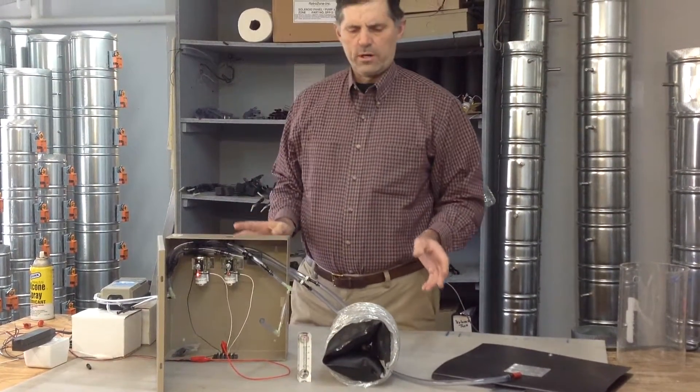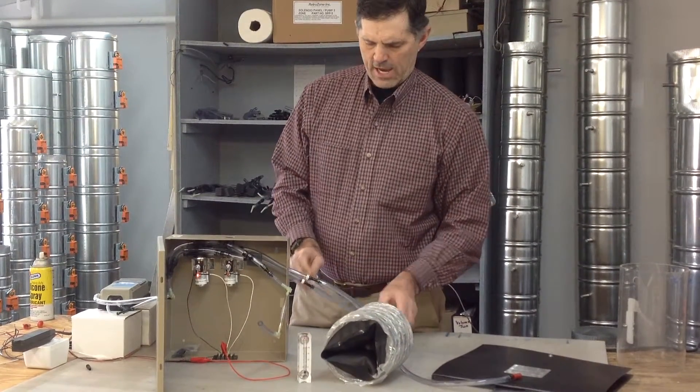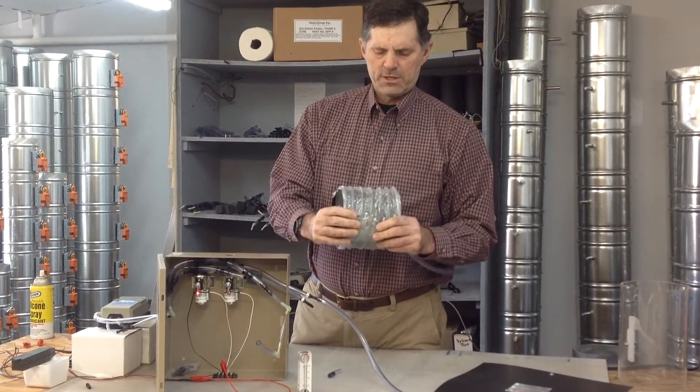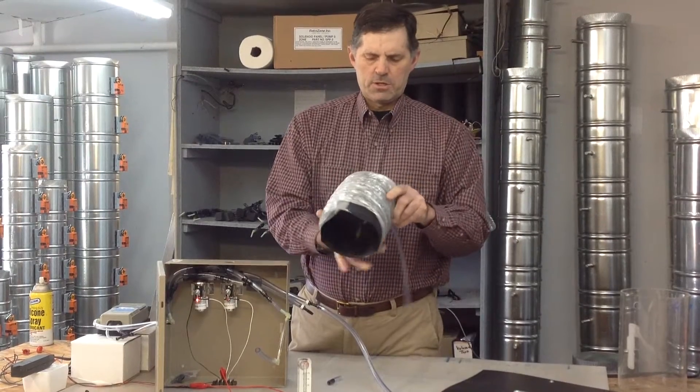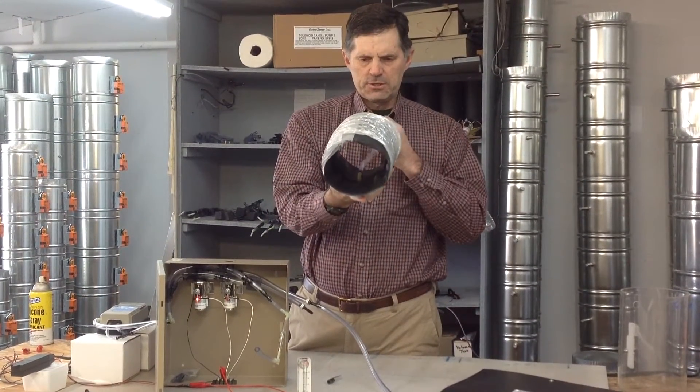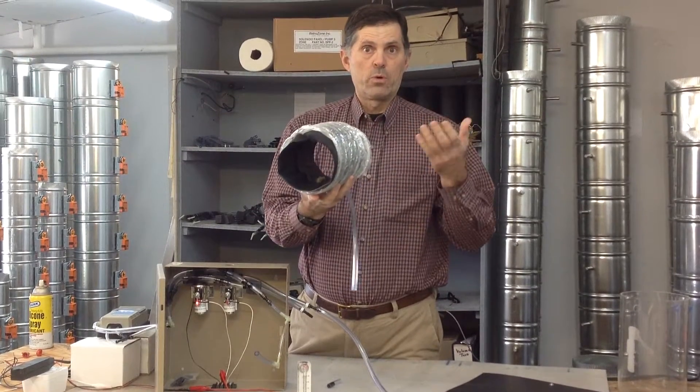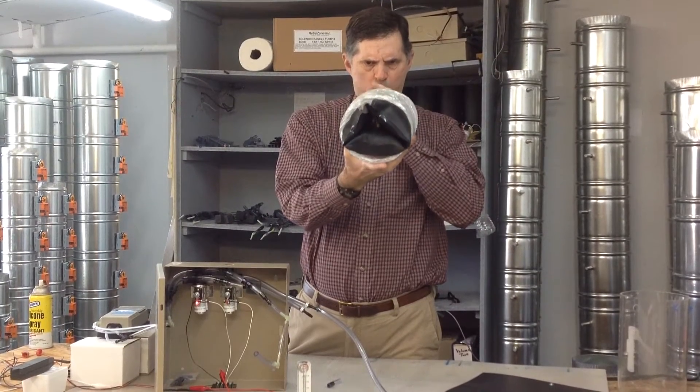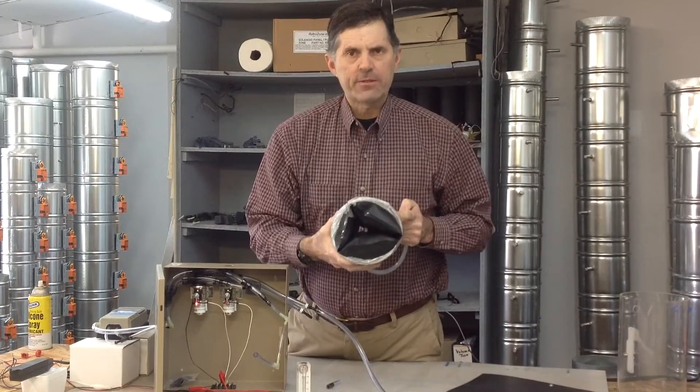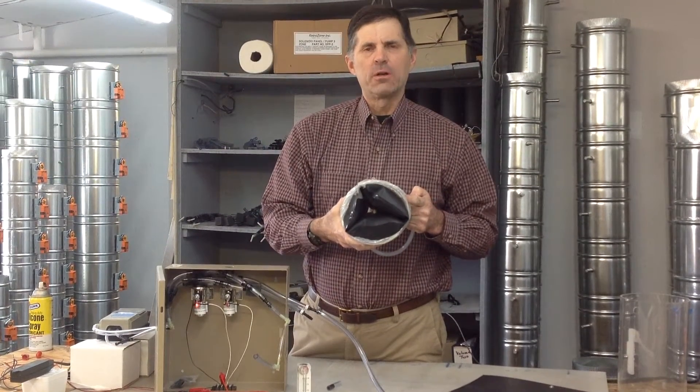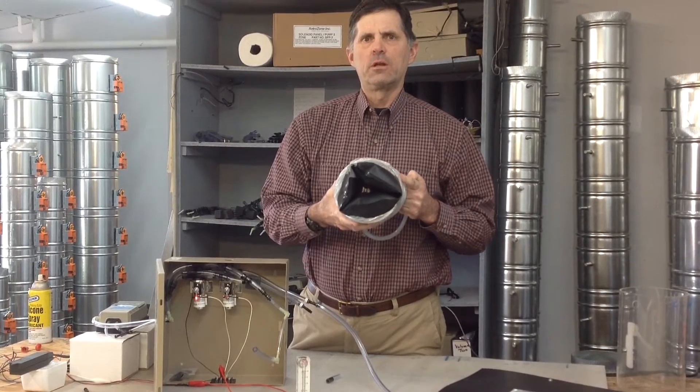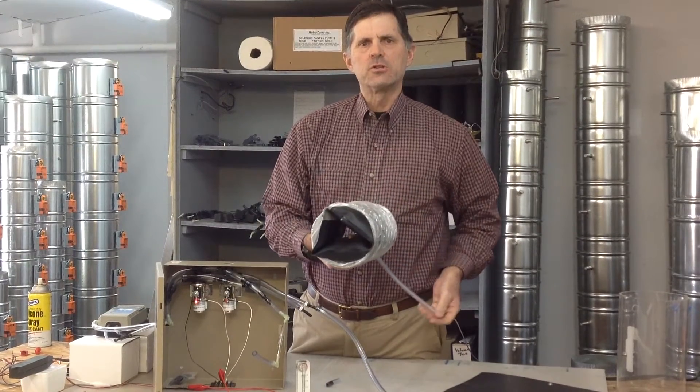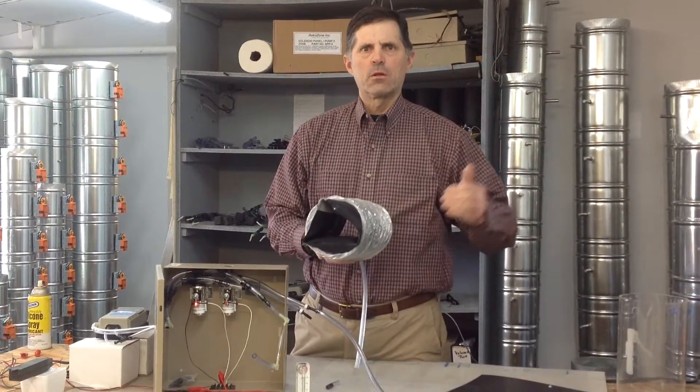Now, the old way of doing this was, I want to point this out, it's actually very possible on these dampers, since they only use about a half a PSI. If you don't have the test instrument, it's actually, frankly, very easy to blow these things up to about a half a PSI, which is about what we can comfortably do with our lungs. Now, as you would expect, they'll just get to a point where they won't take any more air. But if you have a circuit, and you continue to try to inflate them and inflate them, and they just keep bleeding down and keep bleeding down, that's another good sign that you've got a leak in the system, and it's time to go track that particular circuit down.